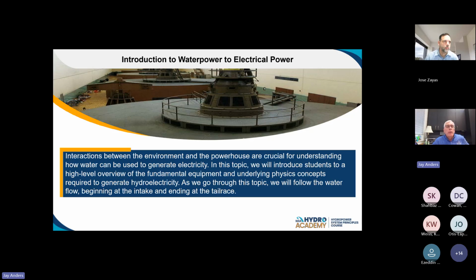Anyway, you can see what's inside here. We have my excitation system, and brushes inside here. The brush rigging basically allows for the voltage control. Voltage control really means excitation control, means voltage control, means VAR, volt-ampere-reactive control, and we'll talk a little about that.